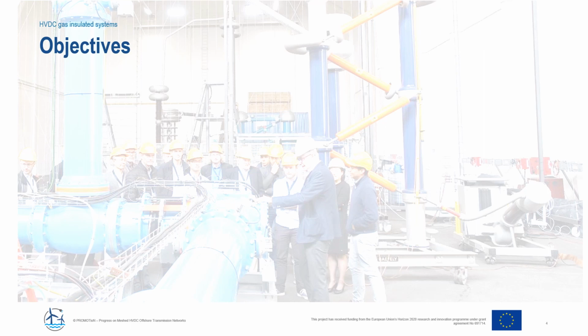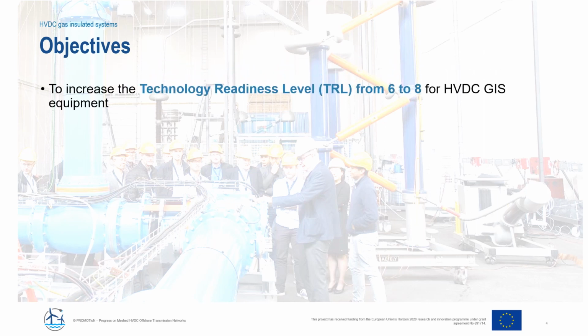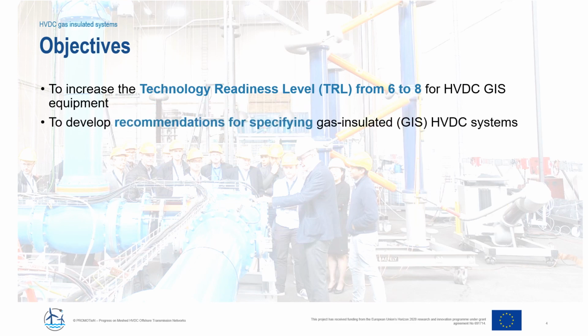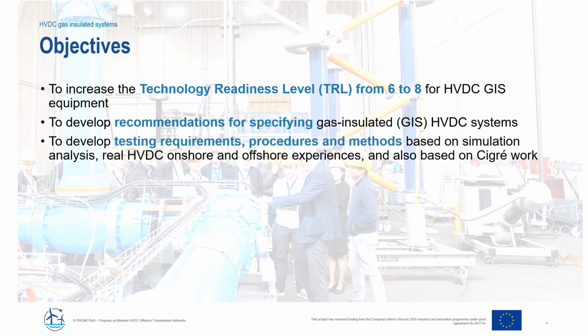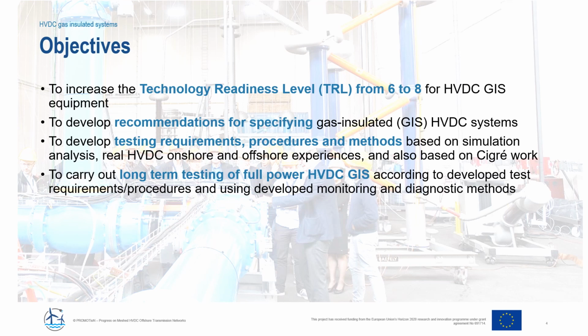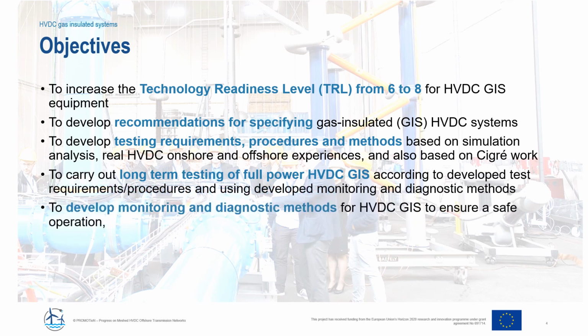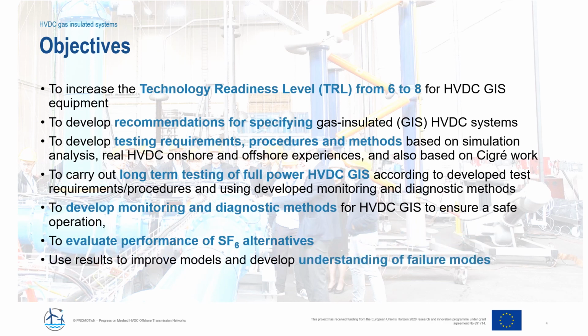Work Package 15 has been formed to make a substantial contribution here: to increase the technology readiness level for HVDC GIS equipment to the highest level, and to develop recommendations for specifying and testing gas-insulated HVDC systems. We develop testing requirements, procedures and methods based on simulation analysis, real HVDC onshore and offshore experiences, and also based on the work of others. The focus of our task was to carry out long-term tests of a full power HVDC GIS according to developed test requirements and procedures, using developed monitoring and diagnostic methods. Furthermore, we had the following tasks: to develop monitoring and diagnostic methods for HVDC to ensure safe operation, to evaluate the performance of SF6 alternatives, and finally, to improve models and develop the understanding of failure modes.